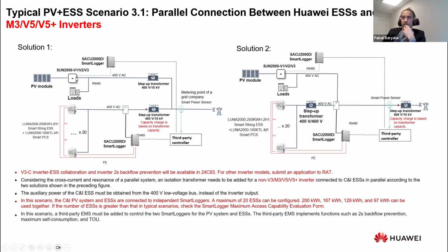This extra smart logger connects to and controls the PV inverters, while the second smart logger or SACU controls the ESS side of the project. These two smart loggers or SACUs are further connected to a third-party control system, which will be the ultimate control unit. This control system should be able to perform extra functions, sending extra commands, for instance to make it on-grid or off-grid. So this third-party control unit should have certain specifications in order to work for such a system. We will go into the specifications later on.